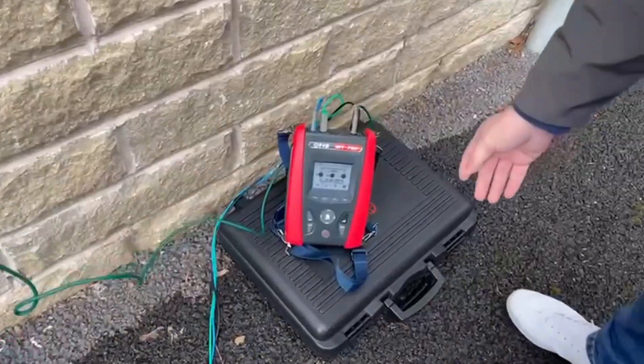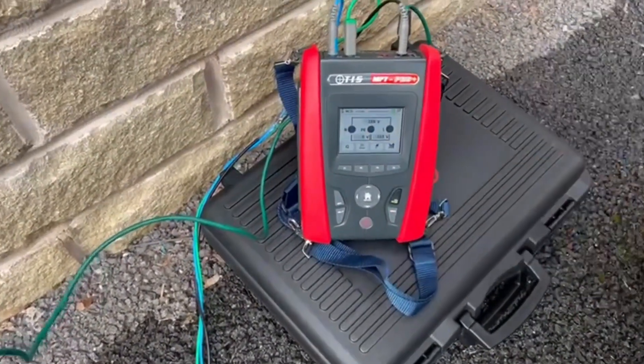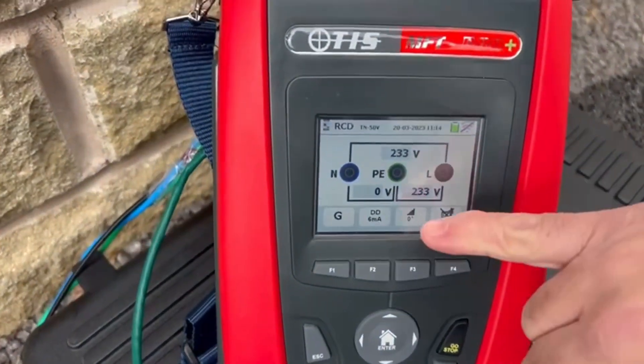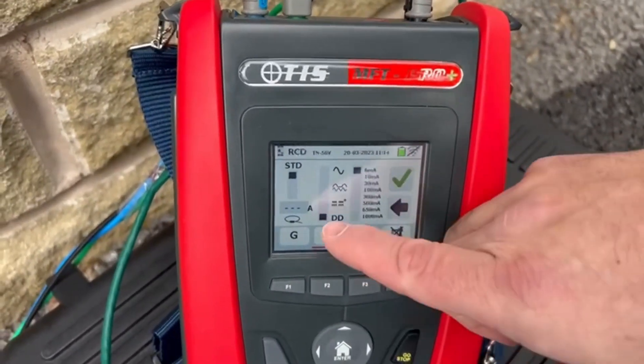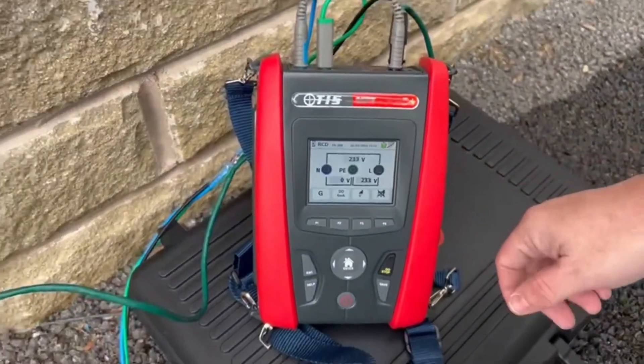This is the OTIS MFT Pro Plus. As you can see I've got the voltage coming through, and it's set to DD 6mA as a ramp test. If I did want to change it and it was a genuine Type B I've got that facility there, but I want to test DD at 6mA — so we tick the box and it's ready to go.